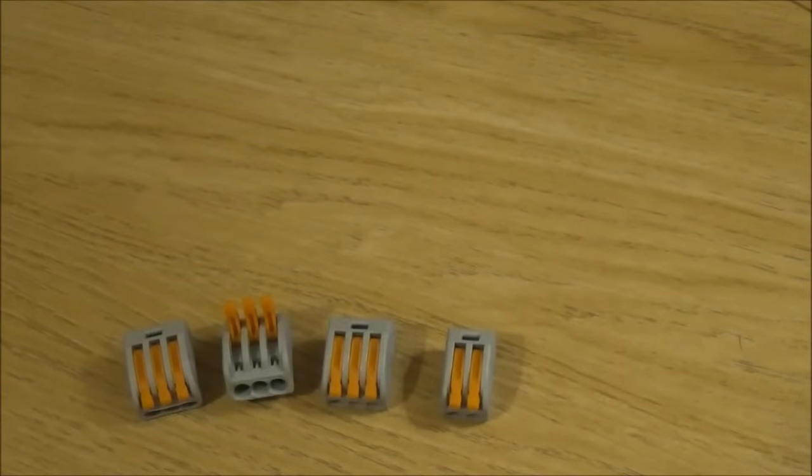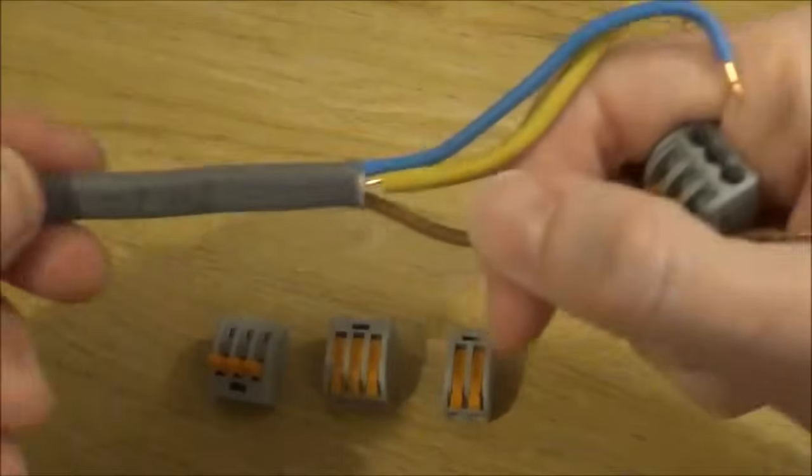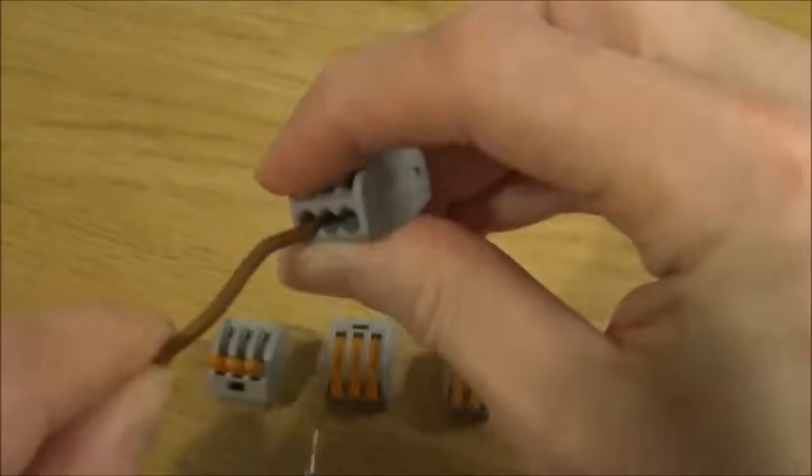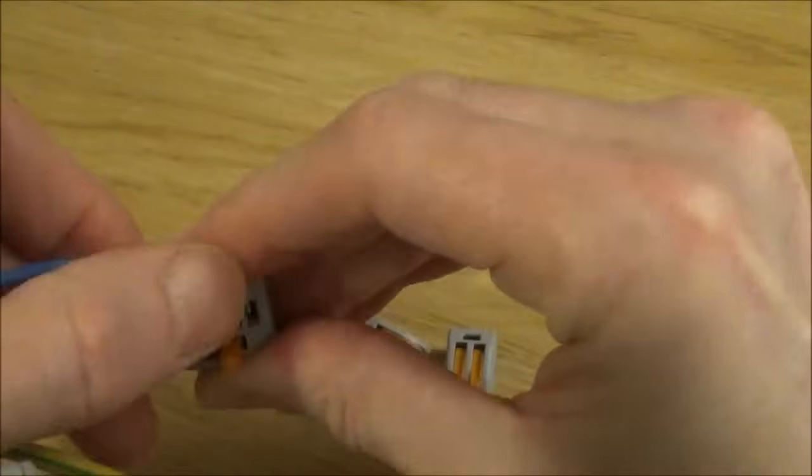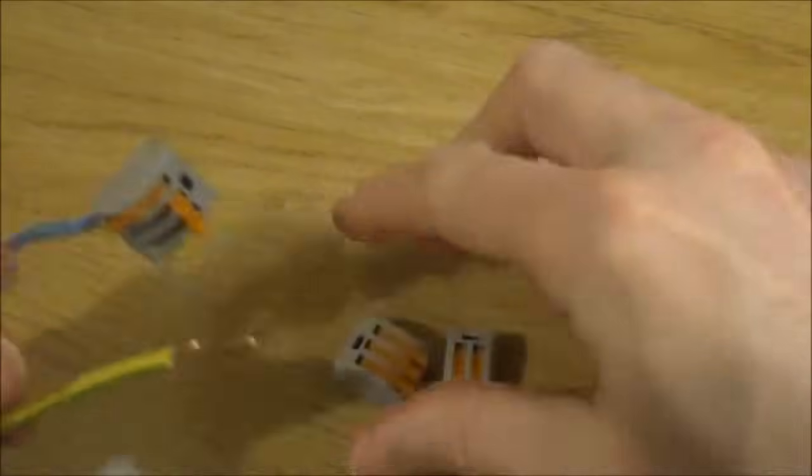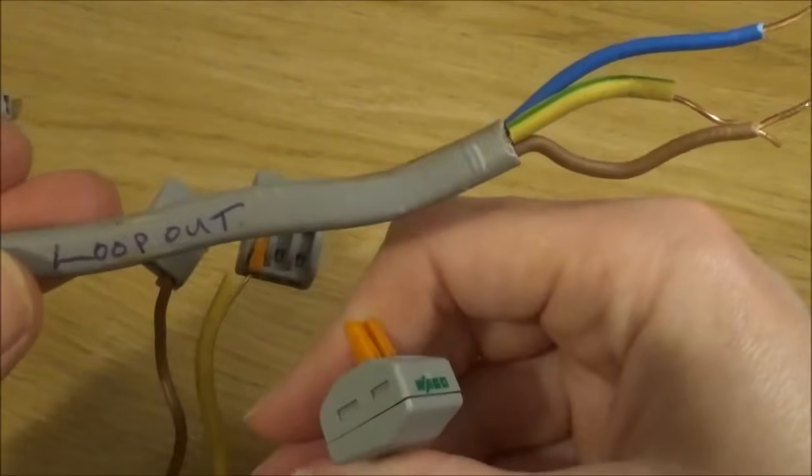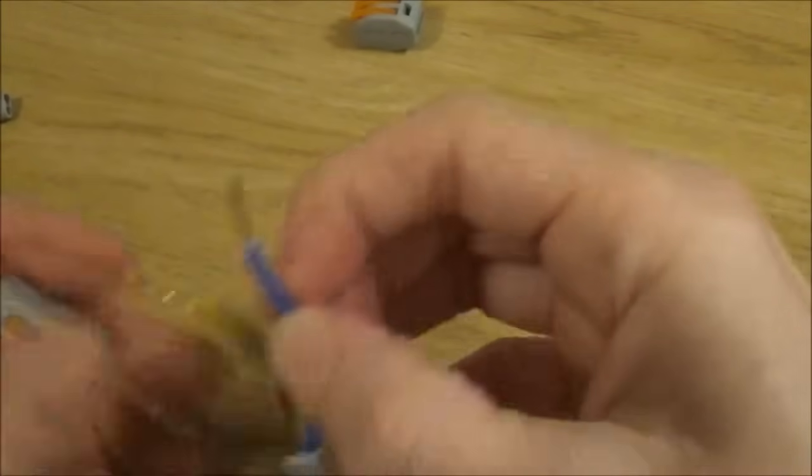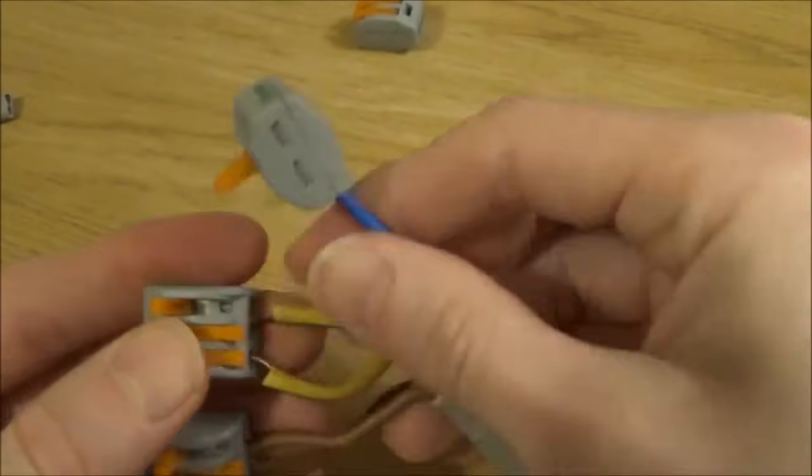These connector blocks are extremely useful when doing lighting circuits. If we treat this as a mock setup for a ceiling light, if we take what I've labeled as my loop in you can put your live into there, your neutral into the next connector block and the earth into the earth connector block. You can then take your loop out, connect the live to the live, connect the neutral to the neutral, and connect the earth to the earth.